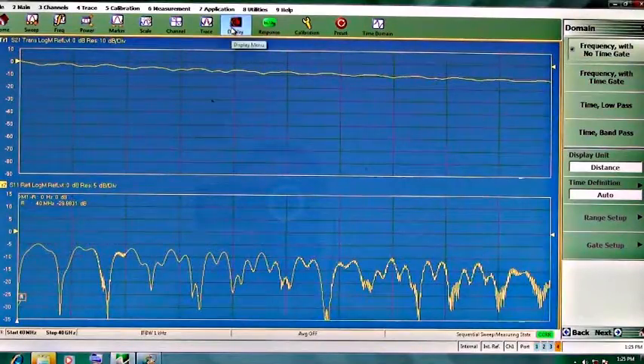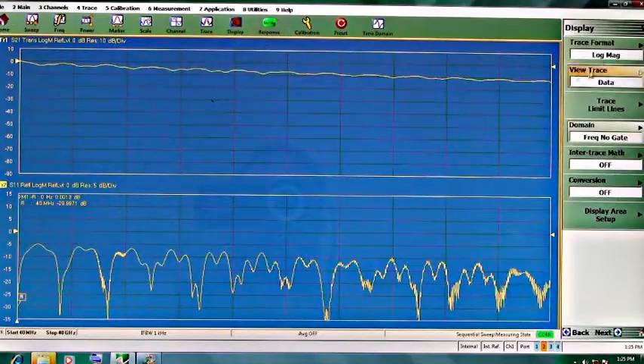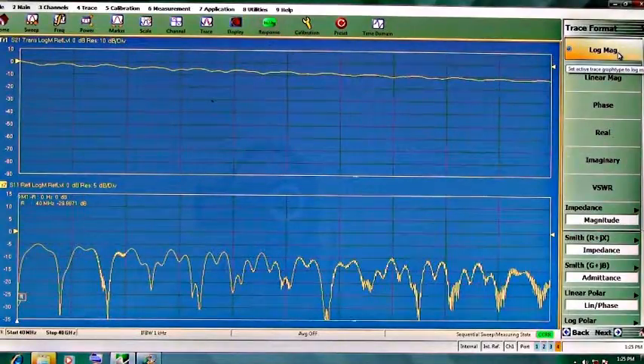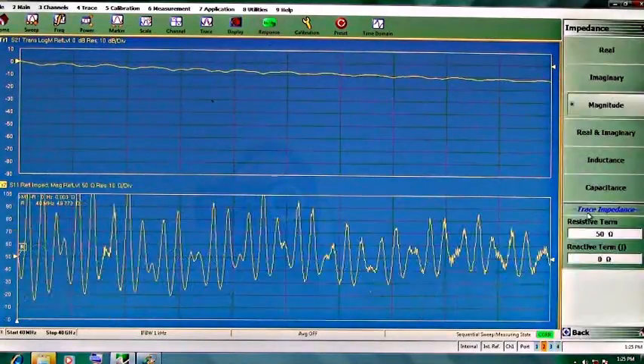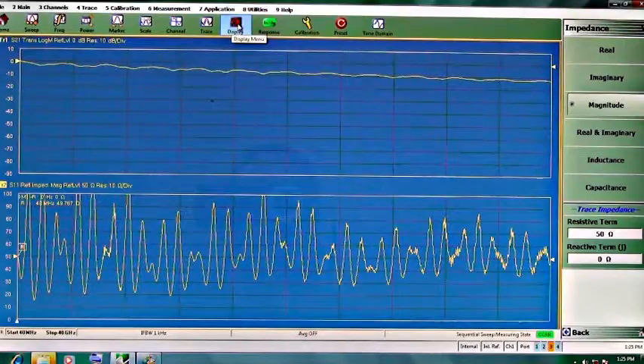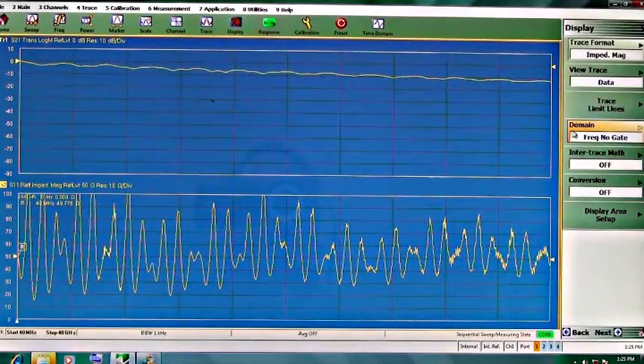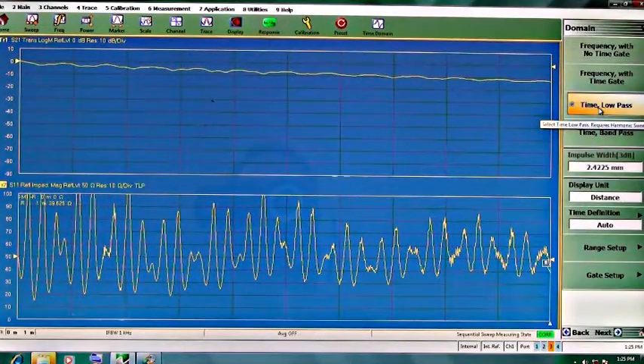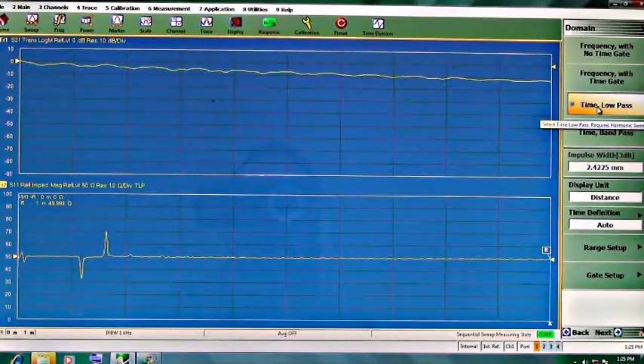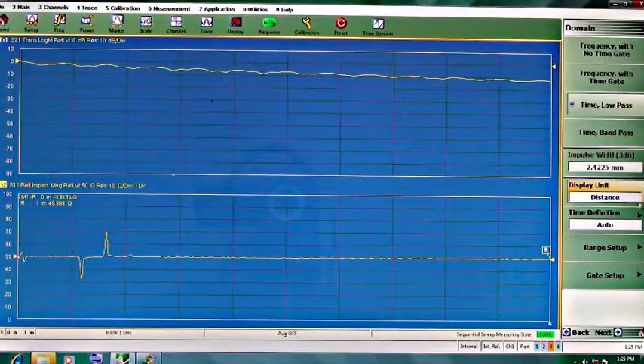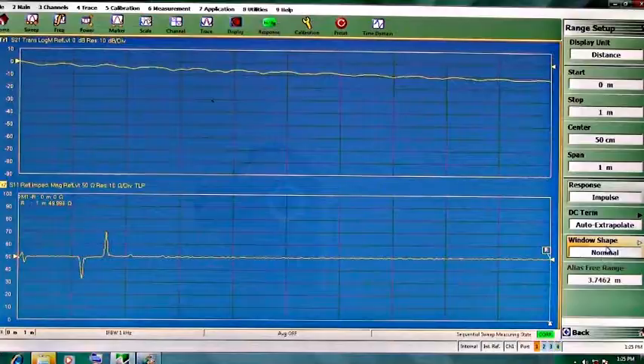So to get into that menu, we'll select display. We're going to go into impedance mode, and look at impedance magnitude so we can read the ohms directly off of the standard. So go into time domain. We're going to select low pass time domain so we can look at it as if we were looking at it with a TDR. We're going to look at the range to make sure our range is set up.